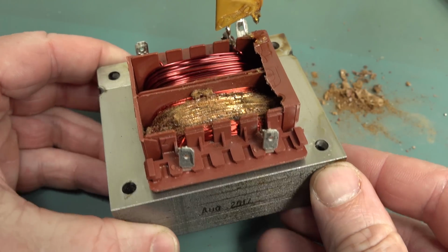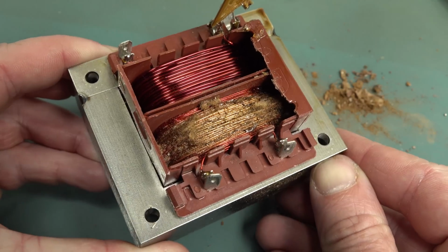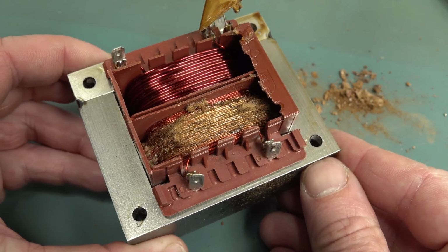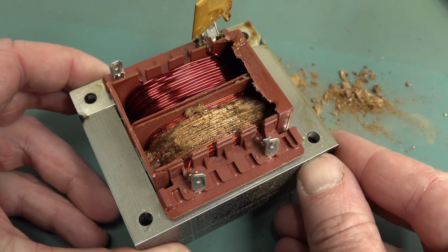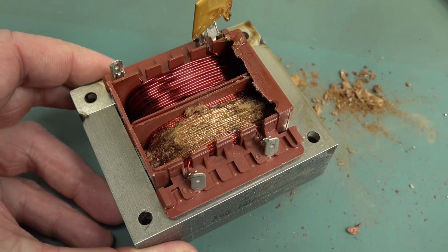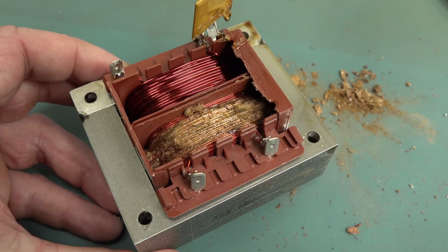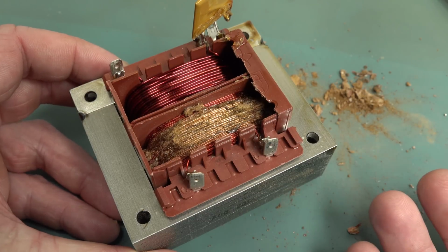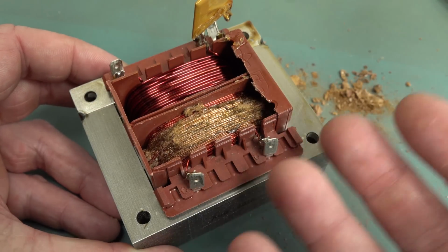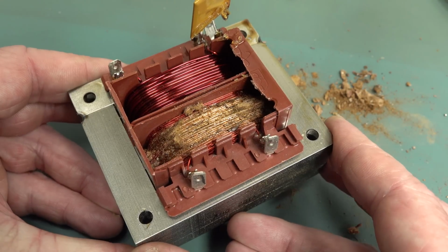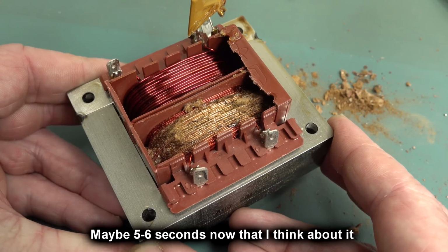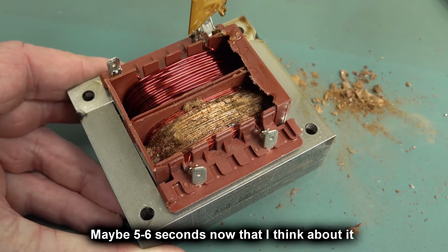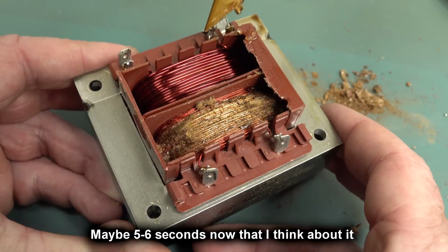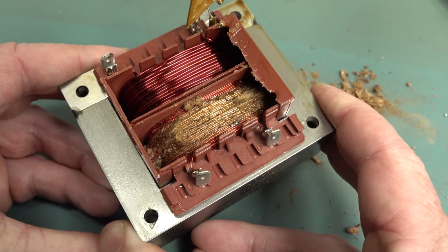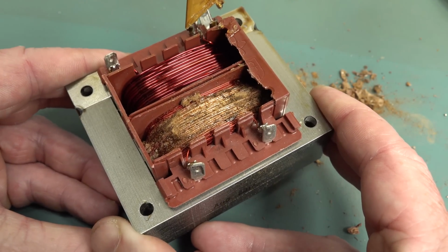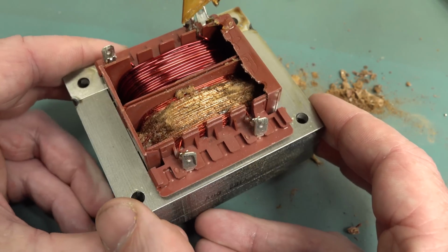Nice, and well, I've got to ask, how did this actually happen? Because you're plugging 240 volts into a 110 volt transformer, double the voltage on the output, of course that means for a resistive element load that we've got here, roughly that's going to be four times the power. So okay, it's going to be delivering four times the power, but surely this thing started smoking literally 2 or 3 seconds after I plugged it in. So even if it would have probably started applying power to the heating element straight away, how it was able to just completely melt the insulation like that after a couple of seconds at four times the power, I don't know.